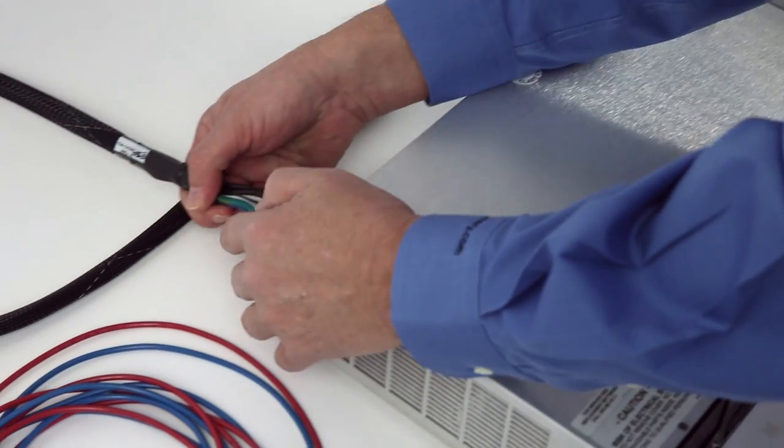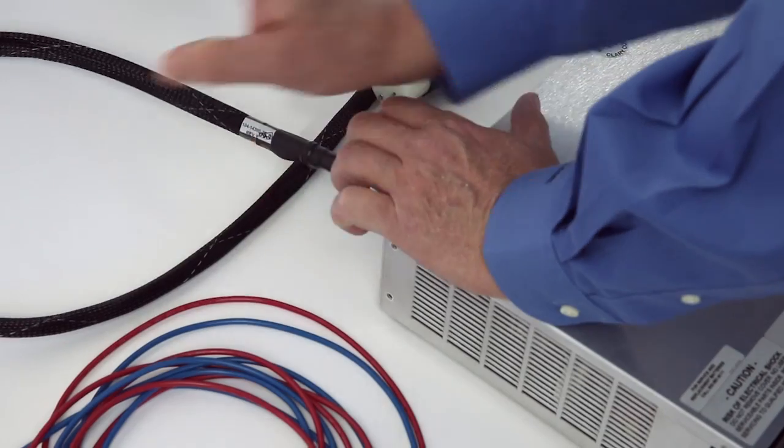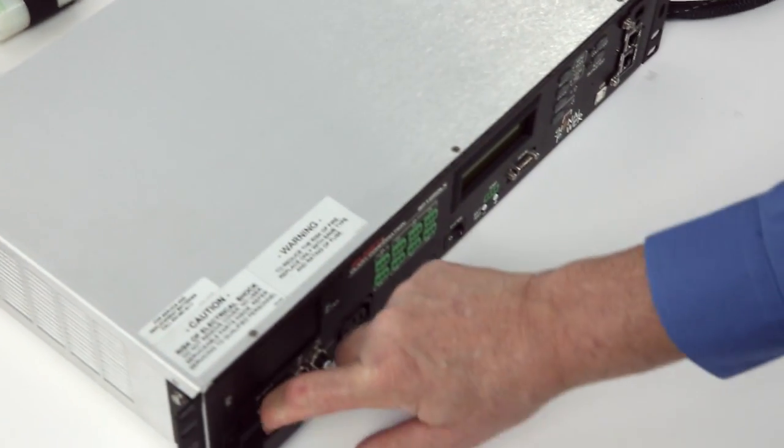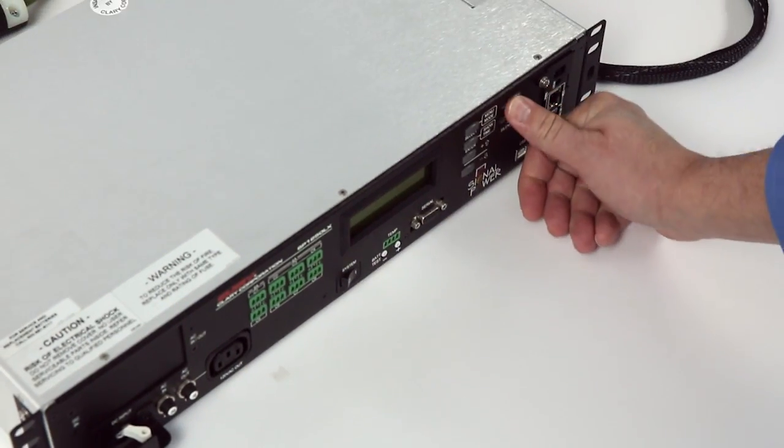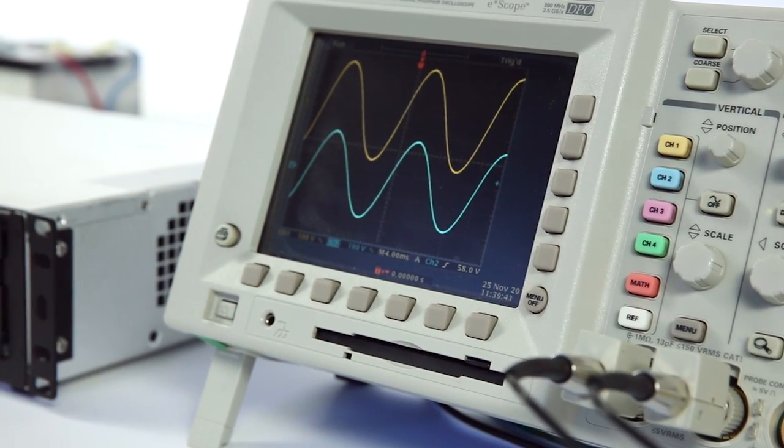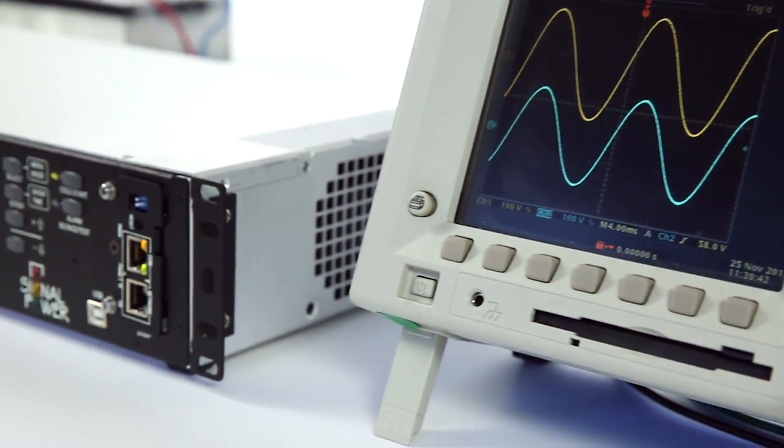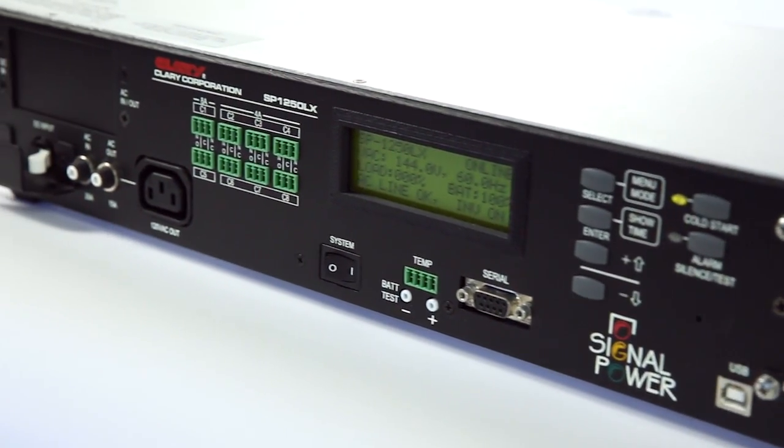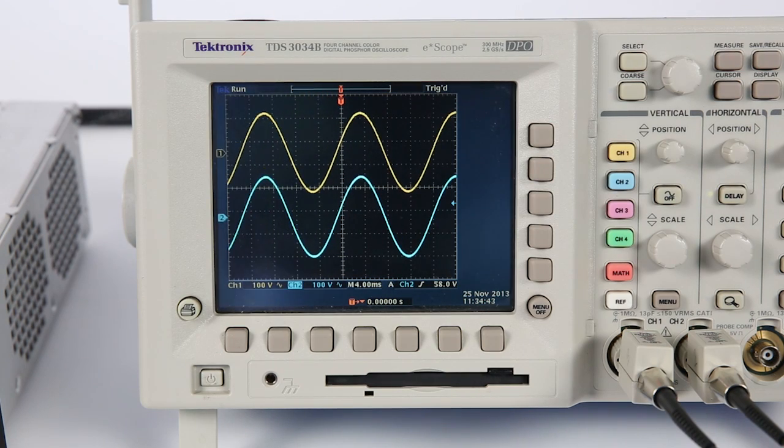To demonstrate Clary's uninterruptible power supply for traffic applications, power conditioning and backup power supply, we have set up an AC power source generator to input wave anomalies. The oscilloscope displays the input and output frequencies and demonstrates how the Clary UPS is immune to the input fluctuations. The immunity delivers clean power for all your traffic applications.